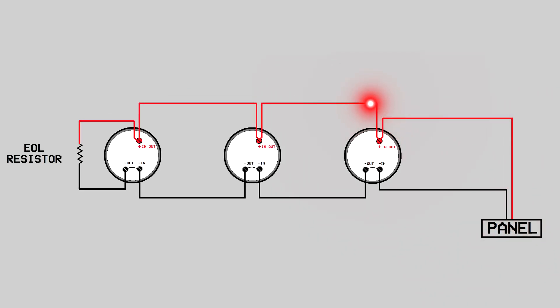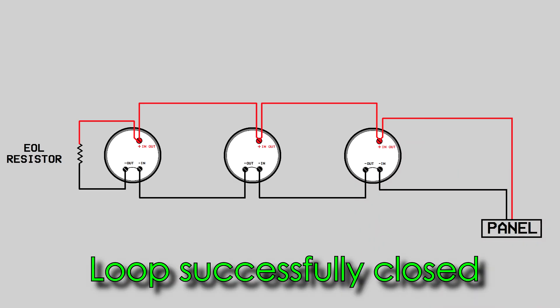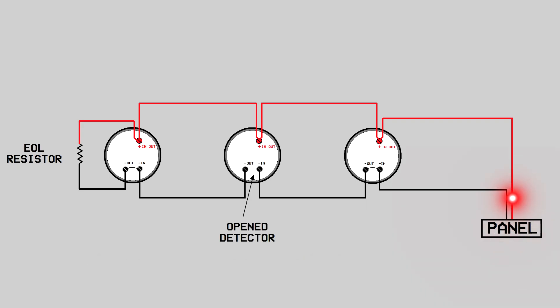Now suppose there is a break in the line after maybe say one or two detectors. How will the panel get to know? To solve this problem there is a concept of end of line resistor that has been deployed here. The end of line or also called as EOL resistor is connected at the last smoke detector. This will mean that some current will always be flowing through the closed line via the EOL resistor. The panel will be sensing this current.